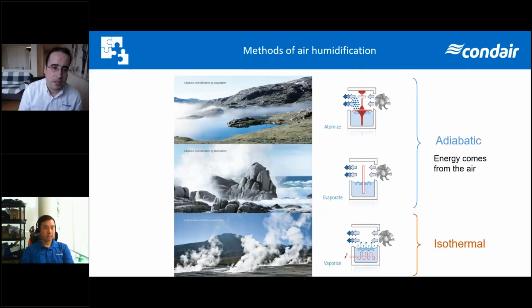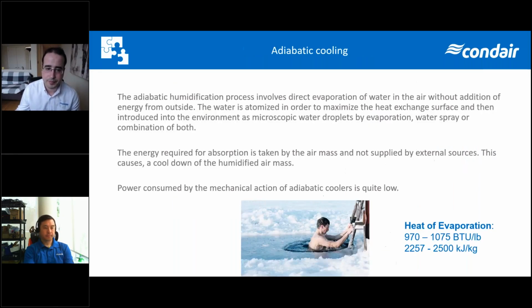Like I said, Condair is primarily a humidification company, but we also do a lot of adiabatic cooling, and adiabatic cooling is connected with adiabatic humidification. It's the same principle, right? Typically in humidification, you have isothermal, like steam, where you boil the water, or you have adiabatic humidification. Adiabatic humidification can be atomization, like droplets, or evaporation, like media systems. This is what we're going to focus on today in our applications: mostly media systems, because that's what's typically used in data center applications and in data centers.